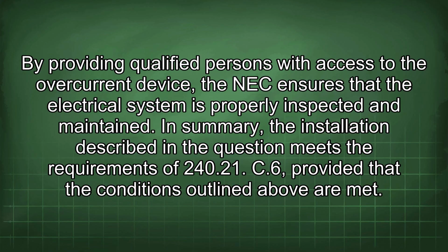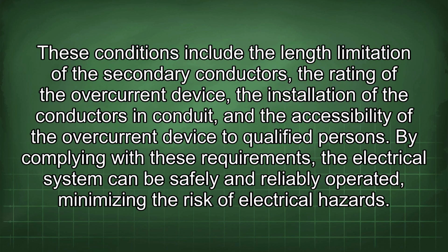In summary, the installation described in the question meets the requirements of 240.21(C)(6), provided that the conditions outlined above are met. These conditions include the length limitation of the secondary conductors, the rating of the overcurrent device, the installation of the conductors in conduit, and the accessibility of the overcurrent device to qualified persons. By complying with these requirements, the electrical system can be safely and reliably operated, minimizing the risk of electrical hazards.